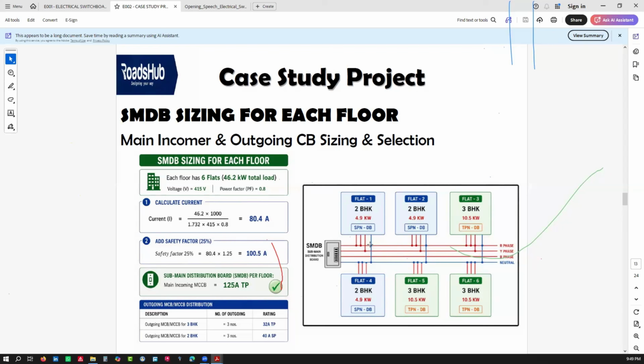So if you're building an SMDB, look at this image on my right. You have an SMDB that is going to supply each flat using what we call a distribution board. So we've said for these 2 BHKs, we are supplying using single phase DBs. But for the 3 BHKs, we are using a three-phase DB. The reason being the power utilization for each flat is different.